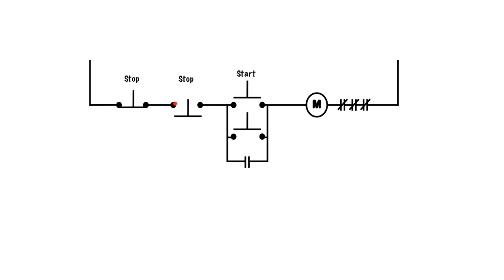Now we'll use the different stop button. We'll use the second stop button to stop the circuit, but it does the exact same thing as the first. It opens up the circuit. Power can't get through that node, so it would de-energize the M coil. It opens up these contacts, and these pushbuttons are being held into their normally open position by the springs anyways. When we release the stop button, there will be no access to energized M coil.